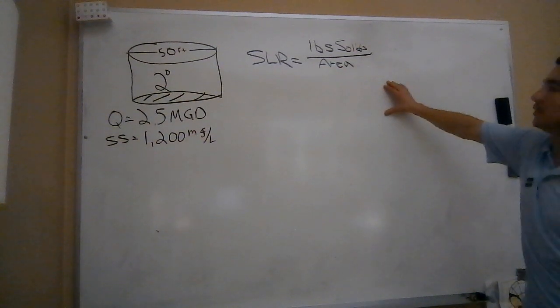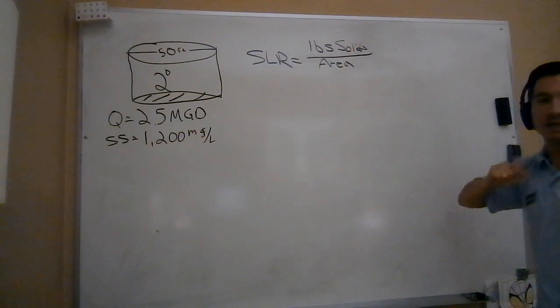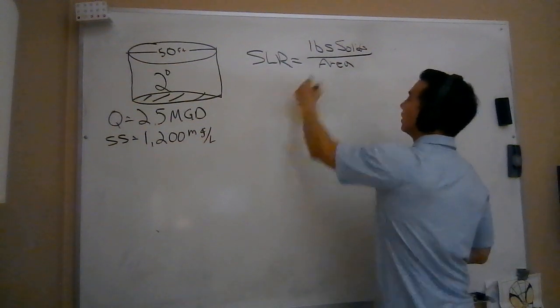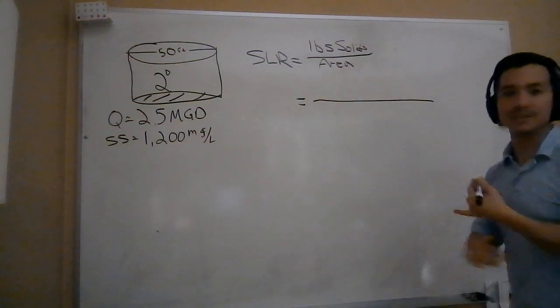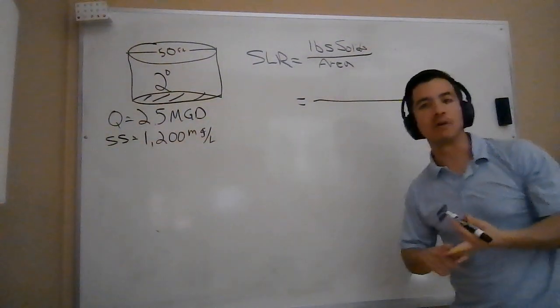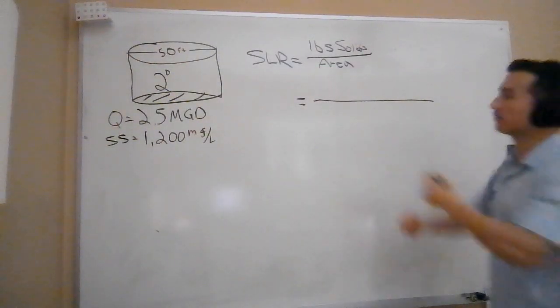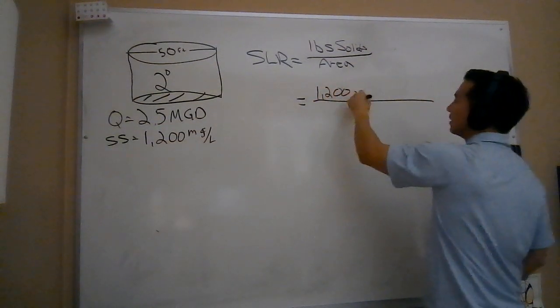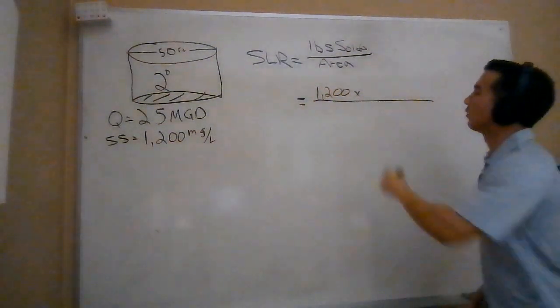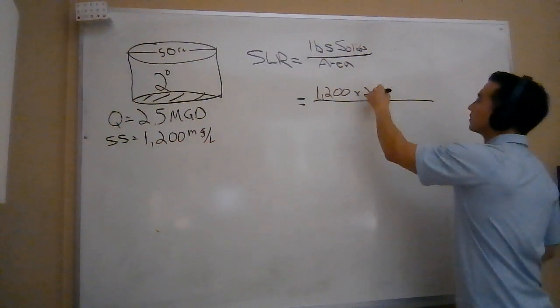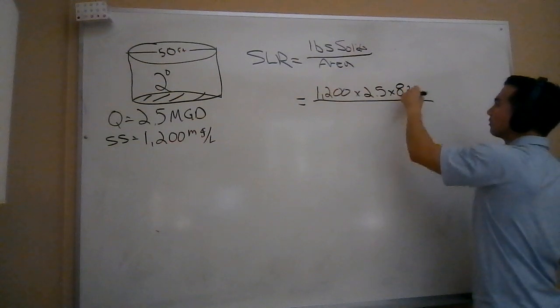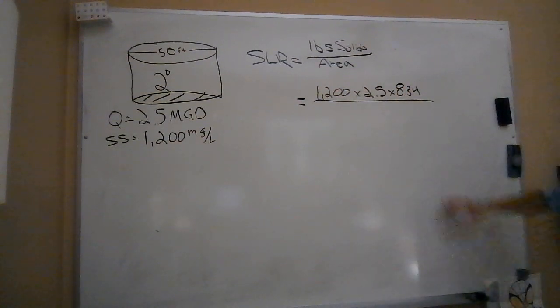When we see pounds formula, we should be thinking pounds formula right away. What do we need? We need our concentration, our volume, and our weight of water. The concentration of our solids is 1200, times my volume or flow of 2.5 million gallons per day, times the weight of water which is 8.34 pounds per gallon. This is going to get me to pounds of solids.